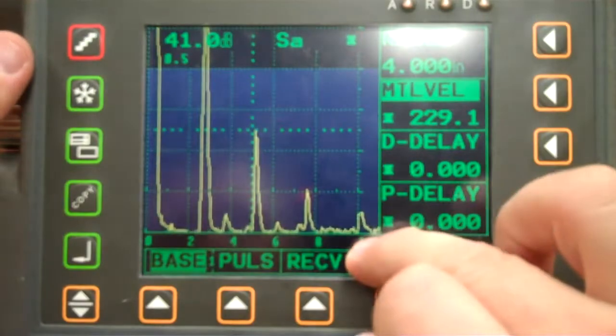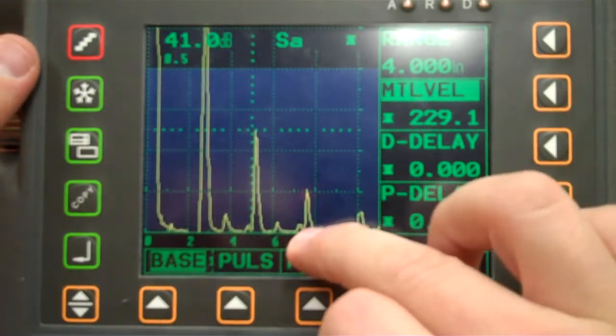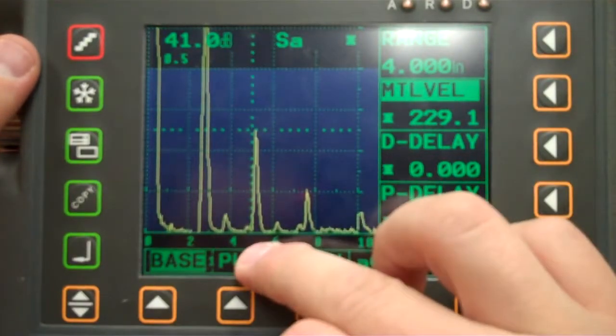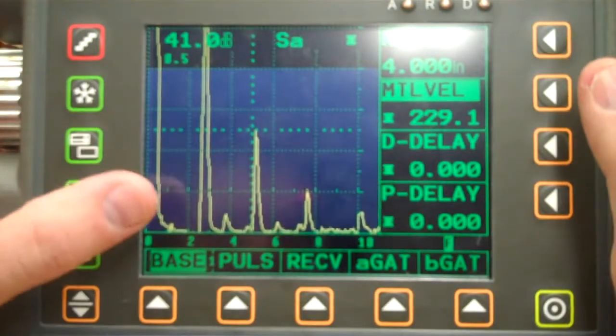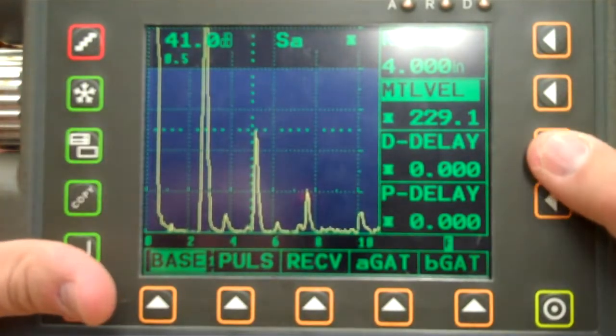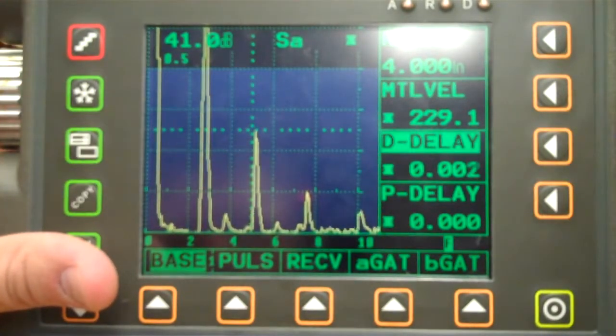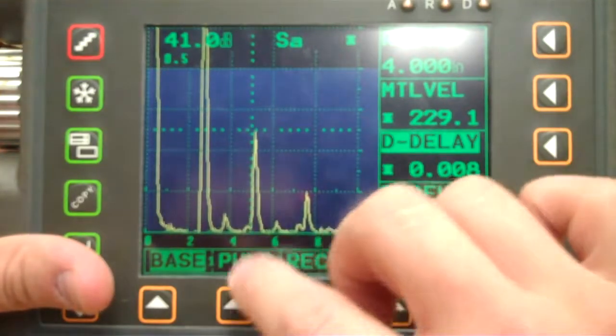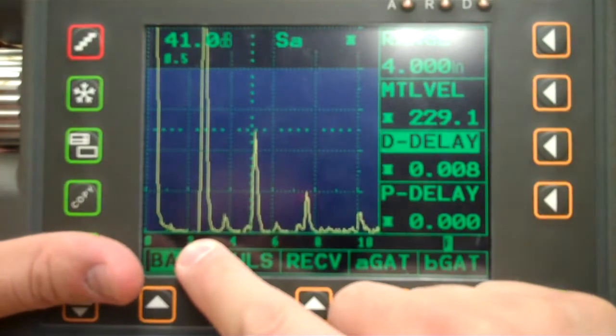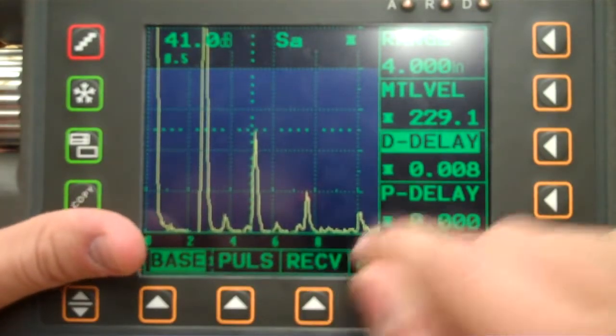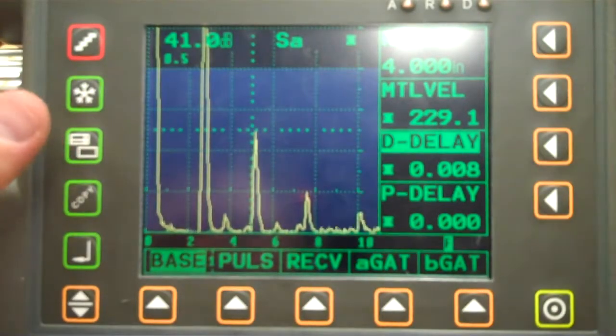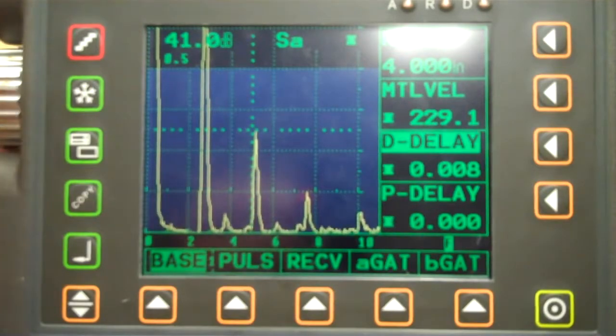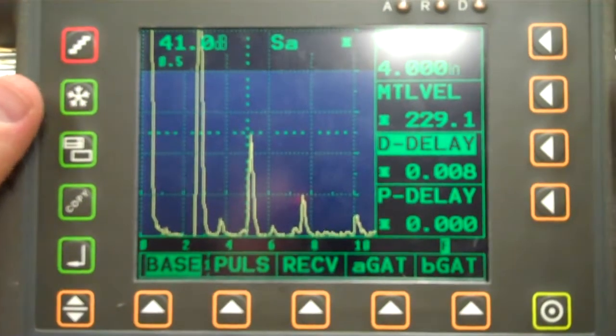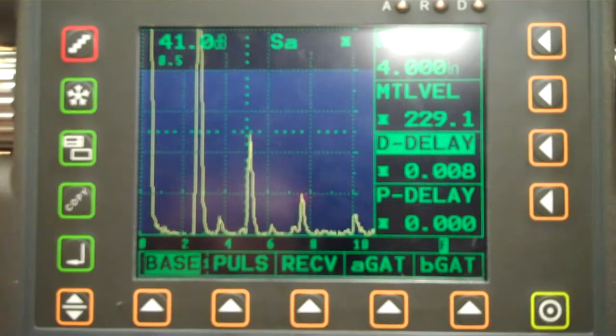Alright, there's my 4 inches right at 100%. Okay, I'm pretty close to 75. I'm pretty close to 50. And I'm pretty close to 25. But let's take this delay, push everything over just a little bit, just because I like to. So now we're right on 50. 25 is still good. 75 is okay, and we're pretty much right on 100 there. So I just pushed the delay over just a little bit, not enough to really hurt us, but just a little bit, so that way we could see what was going on.